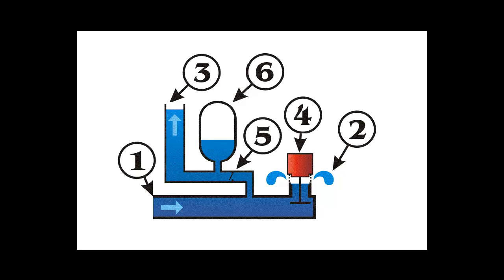A pressure vessel 6, containing air cushions the hydraulic pressure shock when the waste valve closes, and it also improves the pumping efficiency by allowing a more constant flow through the delivery pipe. Although, in theory, the pump could work without it, the efficiency would drop drastically and the pump would be subject to extraordinary stresses that could shorten its life considerably.